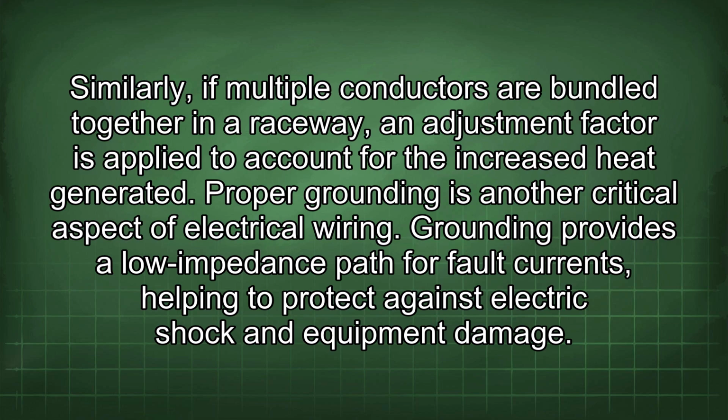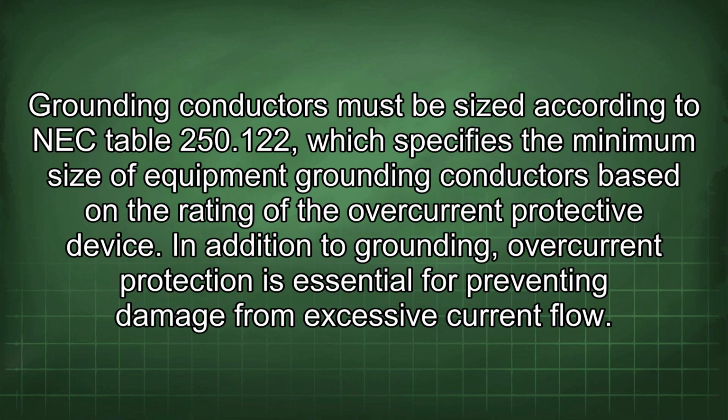Grounding provides a low impedance path for fault currents, helping to protect against electric shock and equipment damage. Grounding conductors must be sized according to NEC Table 250.122, which specifies the minimum size of equipment grounding conductors based on the rating of the overcurrent protective device.